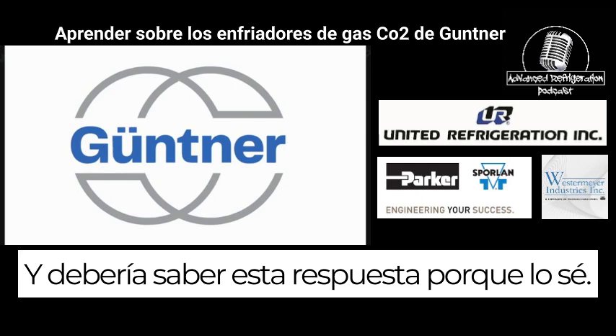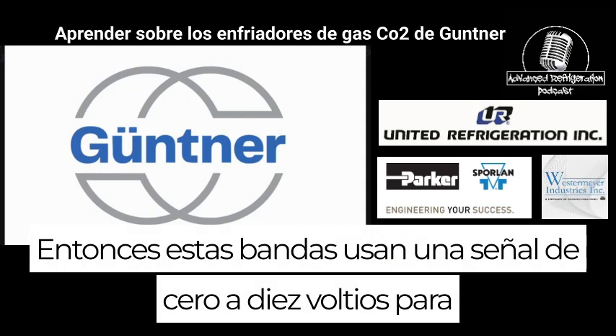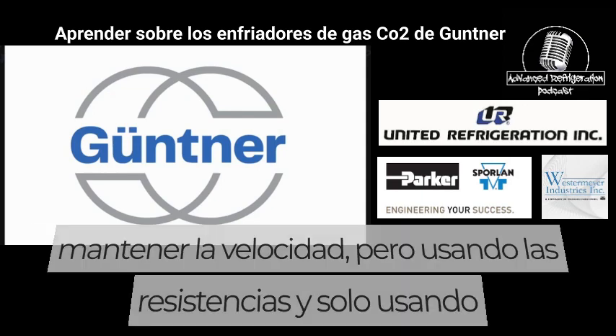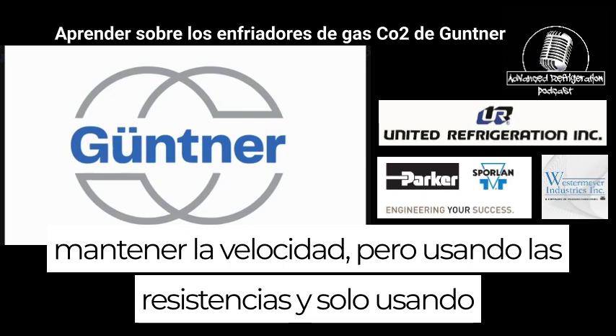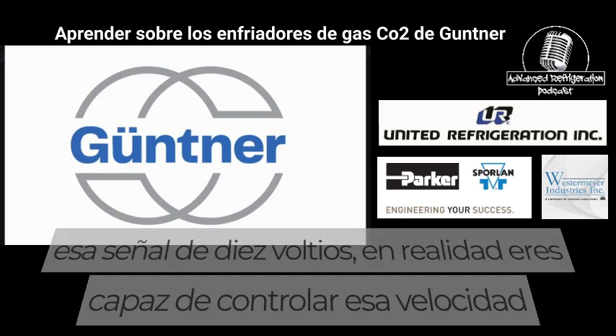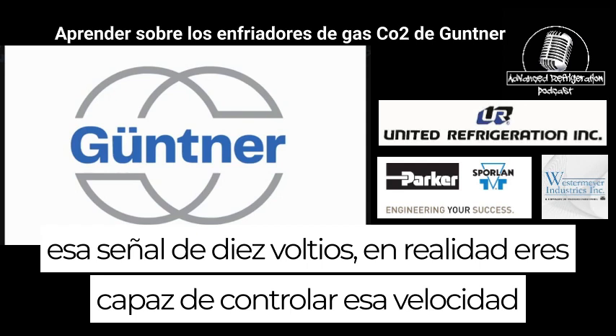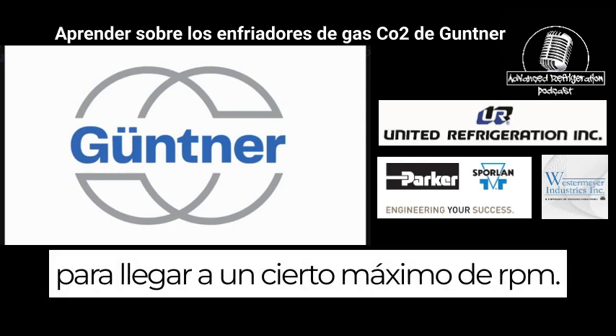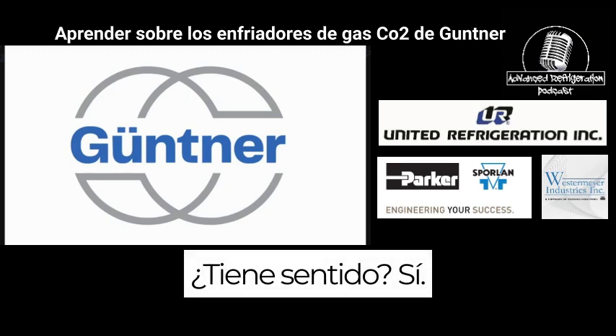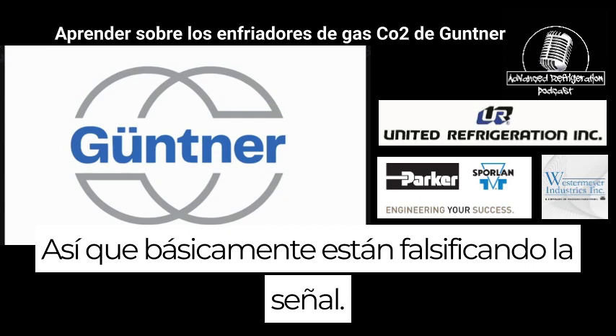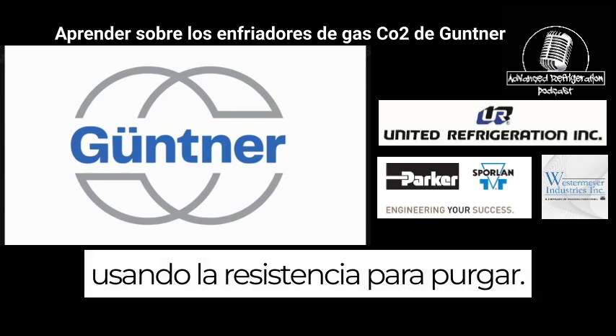I know that these fans use a 0 to 10 volt signal to maintain the speed, but by using the resistors and only using part of that 10 volt signal, you're actually able to limit the speed to a certain maximum RPM. Does that make sense? Yeah. So they're basically faking out the signal by using the resistor to bleed it down.